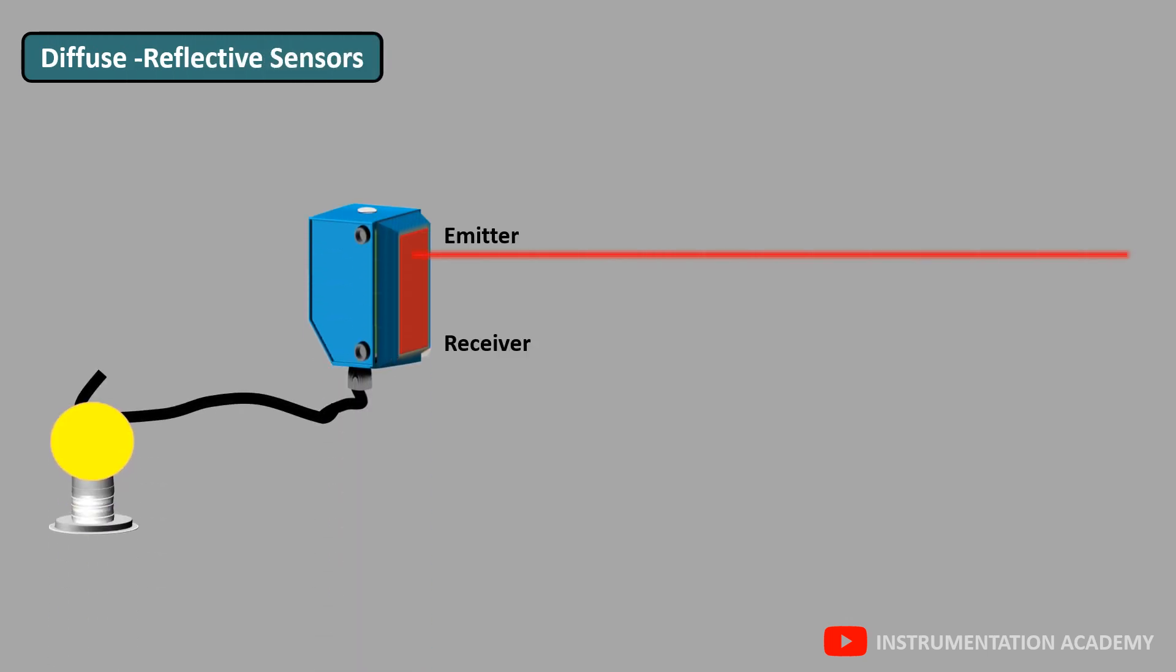In diffuse reflective sensors, as the receiver does not receive the light normally from the emitter, in light on mode, the output will not be energized. So the bulb will be off. While in dark on mode, as the output will be energized when the receiver does not receive the light from the emitter, the bulb glows.